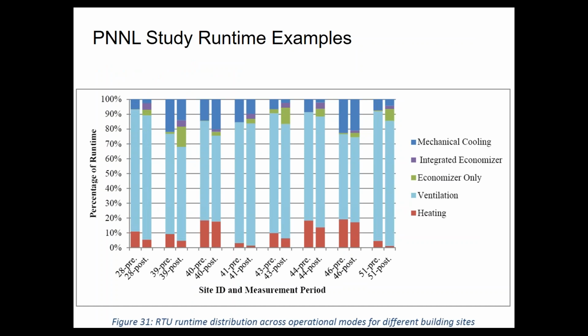You probably have seen this chart before. It comes out of a Pacific Northwest National Lab study published in 2013. And this particular chart is showing you various modes of runtime for packaged rooftop units. Red is how many hours they spent in heating. Blue is cooling. Green is economizer. Purple is integrated economizer. But then baby blue is nothing. No heating and no cooling of any type. It's just occupied hours with the fan running for code ventilation reasons. So as you can see, there's a lot of hours where we're just running the fan and not heating and cooling.